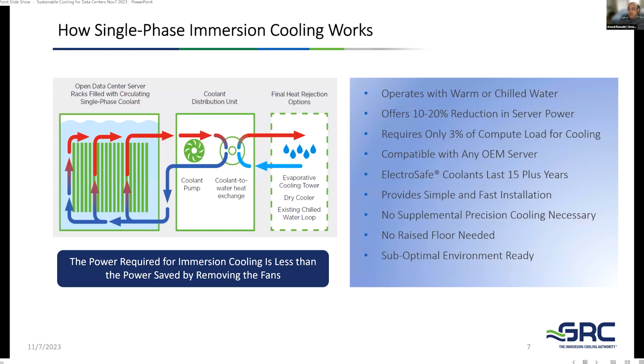Now, because I am not depending on air, we remove the fans from all these servers. The moment I remove the fans, 15 to 20% power consumption is removed, because in a typical server, 15 to 20% is the power consumption of the fans of the server. So the customer starts seeing the benefit of energy efficiency even before we start the data center, right? All the fans are removed. Now I need to move this coolant so that it is effectively capturing the heat. And that is where we use a coolant distribution unit with a pump. So the heat gets captured by this coolant, which is 1000 times more thermally conductive as compared to air.